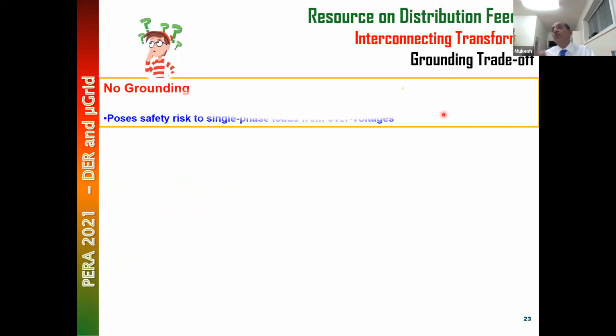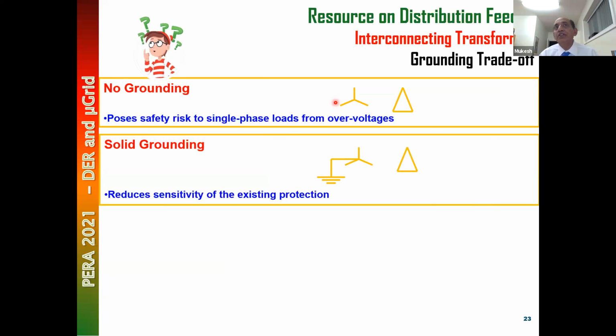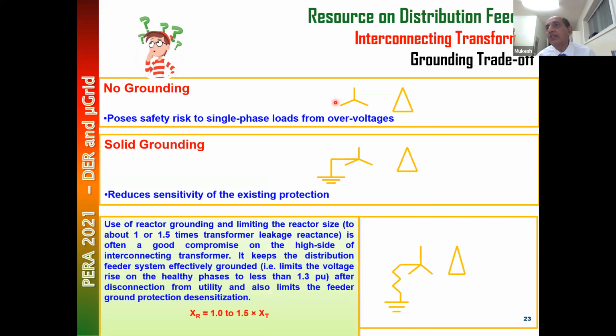So what is the trade-off? How do you overcome this problem? Ungrounded poses a risk to single phase loads. An ungrounded transformer is a risk to the single phase transformer. The grounded transformer reduces the protection sensitivity. So where do we go? There could be a middle path. Do a reactance grounding.